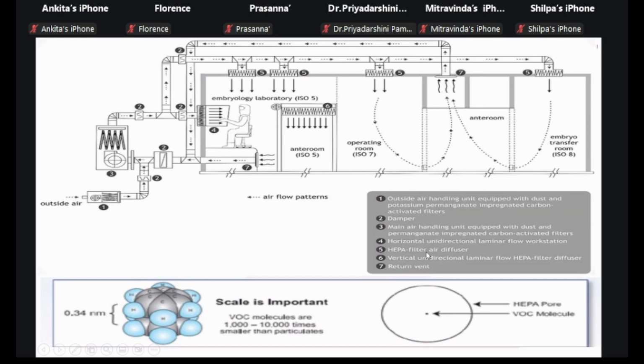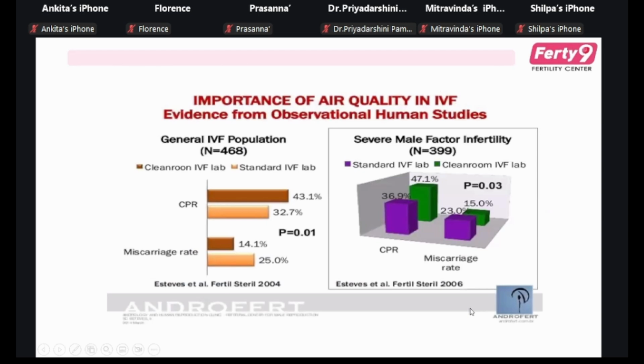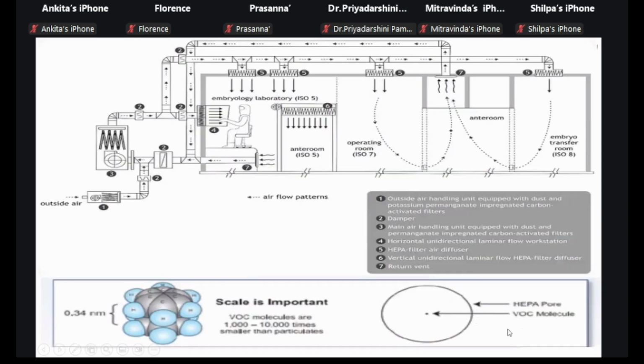A HEPA filter acts like an air diffuser, and most abnormal particles are filtered by it. But the disadvantage of HEPA filters with VOCs is that the HEPA pore size is much larger than VOC molecules - HEPA pore size is around 0.3 micrometers, while VOC molecules are very, very small. So VOCs easily enter the lab even with a HEPA filter present.